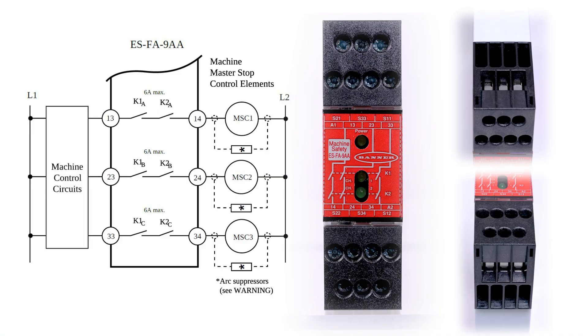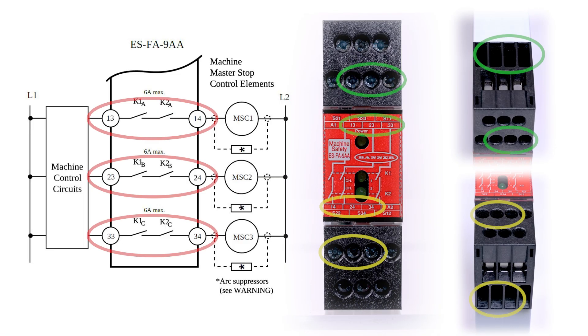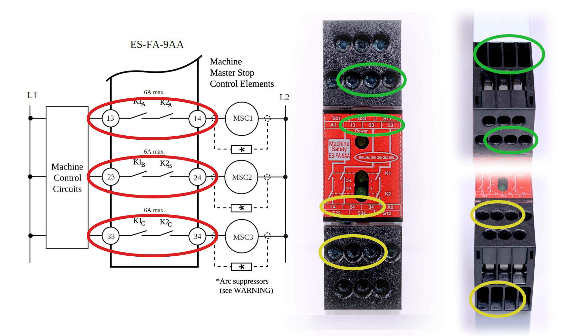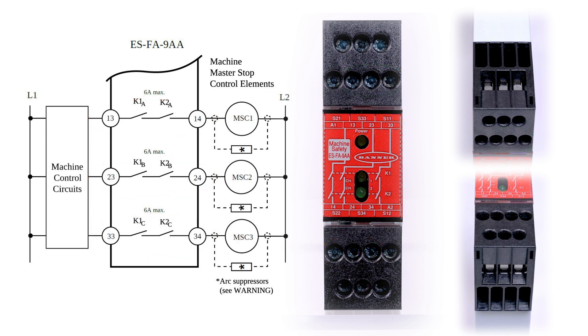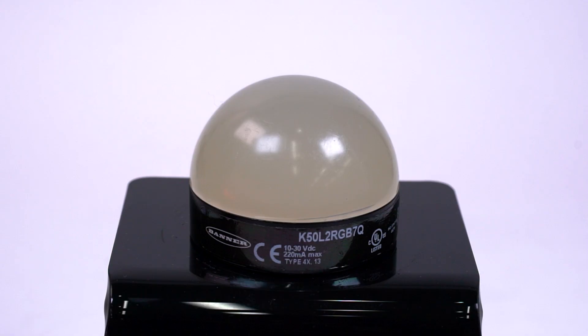The relay module's safety outputs are provided via terminals 13 and 14, 23 and 24, and 33 and 34. Connect the machine control circuits to the first terminal of each pair and connect your machine contactors to the second terminal of each pair. To simulate this, we are using a separate power supply and a K50 indicator.